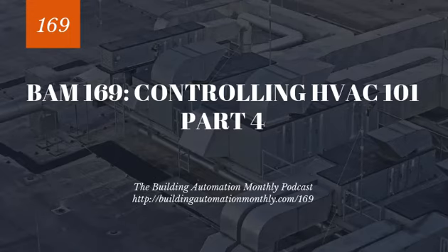Staged control is where you stage on boilers, right? As the temperature drops below the hot water set point, more boilers are brought out of low flow or low fire mode and are brought into control. So these boilers are running maybe in low fire, or maybe they're completely off, which is not recommended. And then they start to fire more, start to heat up more, based on when the supply temperature drops below.